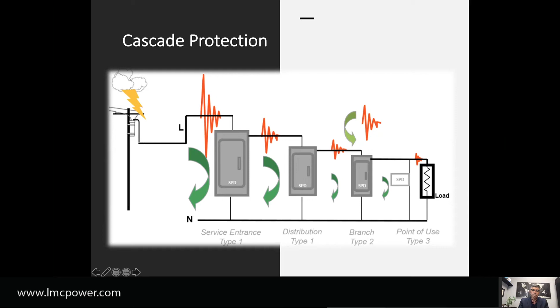Here is the input of the building. Now let me give you some practical experience. This is a recommendation that ASCO sent me. It says SPDs should be installed on the load side of the service entrance, generator, and transfer switch, shown in positions SPD1, SPD2, SPD3, and SPD4. They recommend surge protection everywhere.